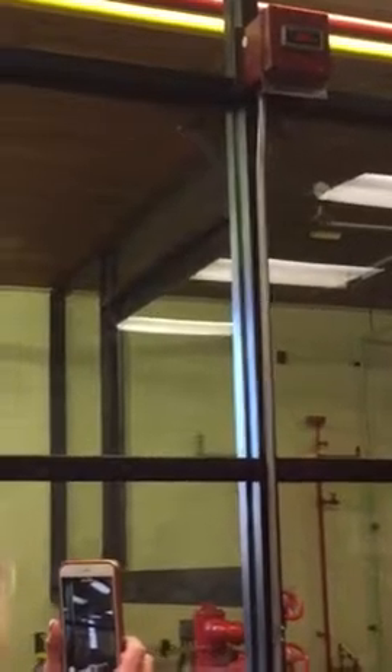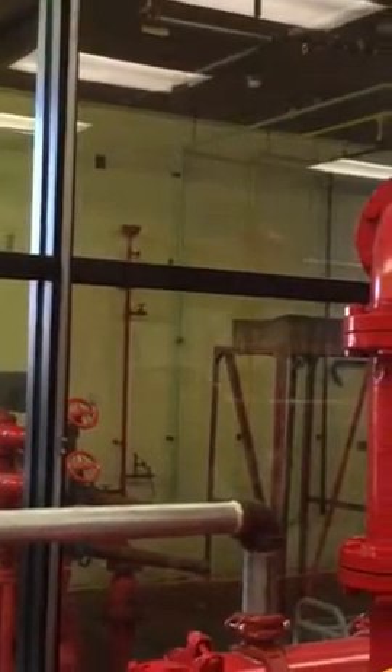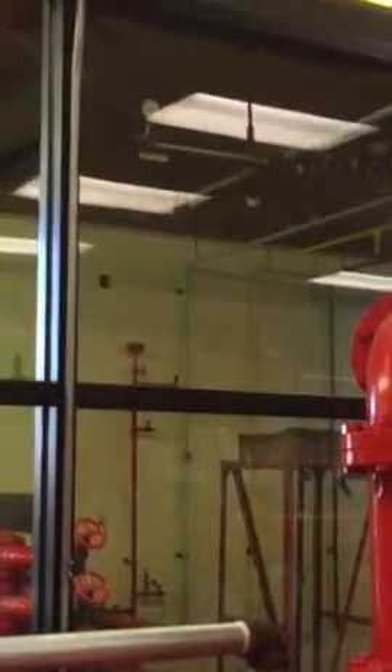All right, so what's activated? Is the strobe next to it? Yeah. Okay, so we don't get a flame detector, we got a heat detector. So the flame detector did not see the flame as of yet. And how's our temperature? Is it getting hotter there? 99. So temperature will rapidly increase.